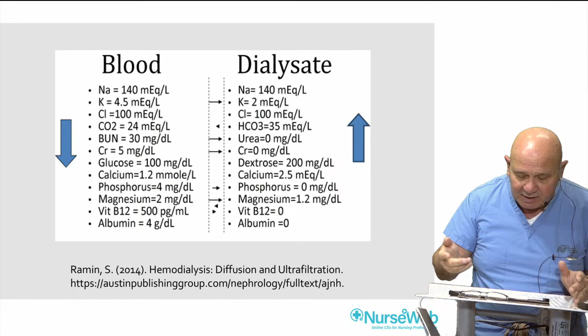Ultrafiltration is the movement of water across the semipermeable membrane using a hydrostatic pressure gradient, or TMP, which is transmembrane pressure. Ultrafiltration accomplishes convection. Pressure on the blood side, inside the fibers, is higher, so water is forced across the pores, and dissolved solutes are pulled with it across. That's called solvent drag. It requires, however, a pump to control it.